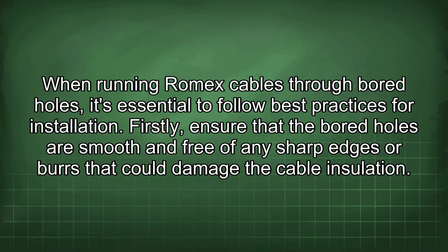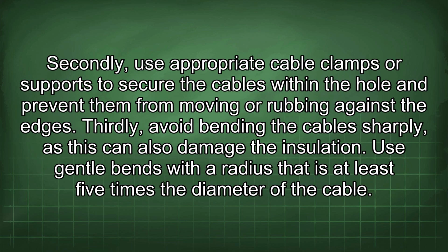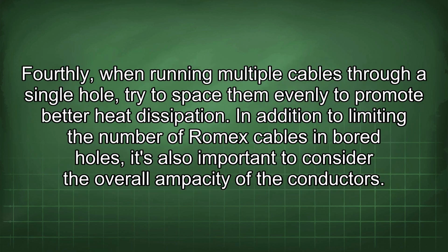When running Romex cables through bored holes, it's essential to follow best practices for installation. Firstly, ensure that the bored holes are smooth and free of any sharp edges or burrs that could damage the cable insulation. Secondly, use appropriate cable clamps or supports to secure the cables within the hole and prevent them from moving or rubbing against the edges. Thirdly, avoid bending the cable sharply, as this can also damage the insulation. Use gentle bends with a radius that is at least 5 times the diameter of the cable. Fourthly, when running multiple cables through a single hole, try to space them evenly to promote better heat dissipation.